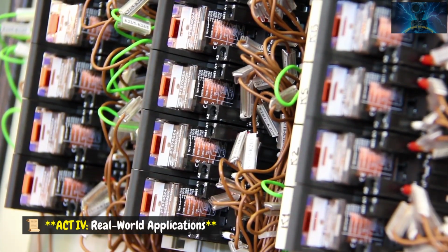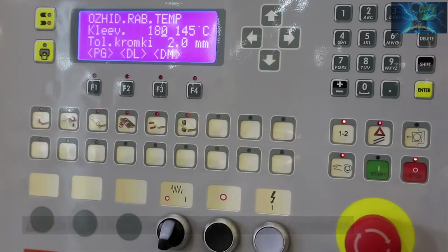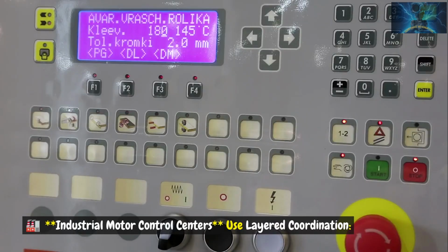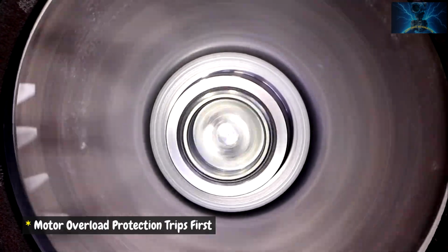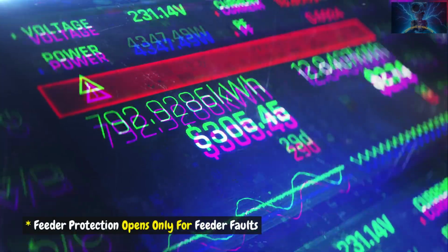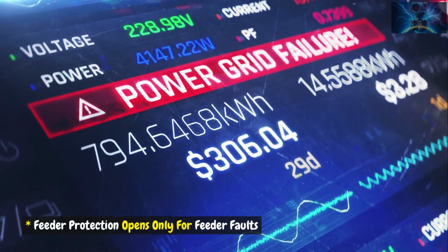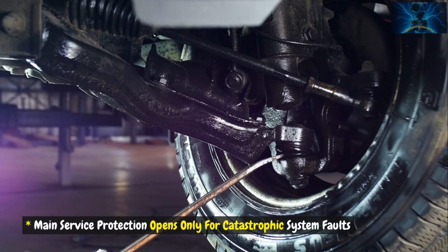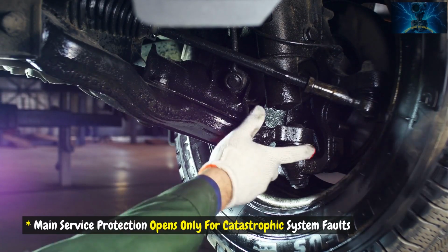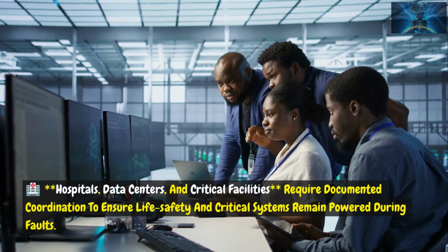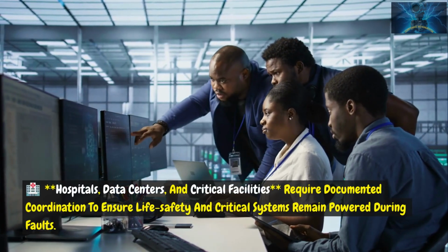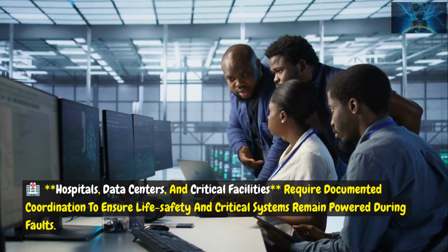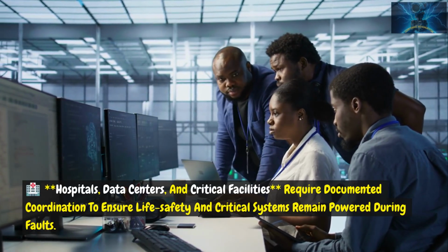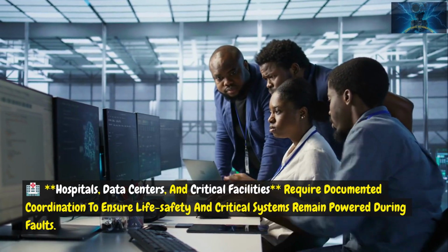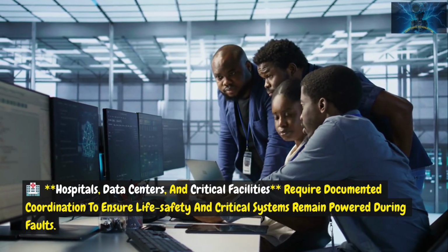Act 4. Real-world applications. Industrial motor control centers use layered coordination. Motor overload protection trips first. Feeder protection opens only for feeder faults. Main service protection opens only for catastrophic system faults. Hospitals, data centers, and critical facilities require documented coordination to ensure life safety and critical systems remain powered during faults.